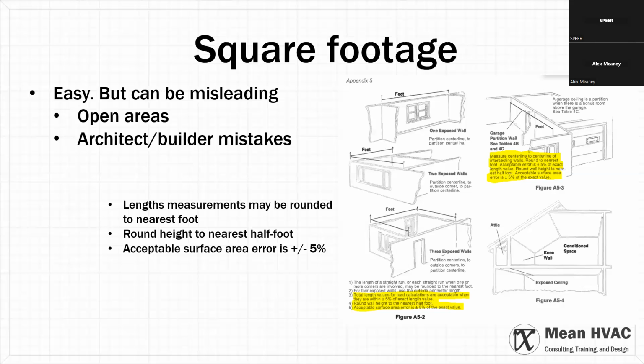So sometimes those things can be explained by that, and it's a simple enough thing to find if they print you the J1, which is one of the recommended printouts from the ACCA. Their inspector liaison or plan review liaison people specifically designed that J1 form for looking over this. You could just find that the room is counted twice and confirm that. I've seen more than you would think: architects and builders not updating the square footage block on their plan when making changes or adding options to a building. So it is something to be aware of, just to zoom out a bit and make sure that's not the case.